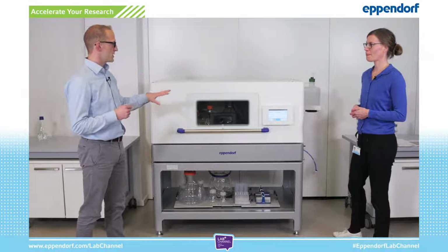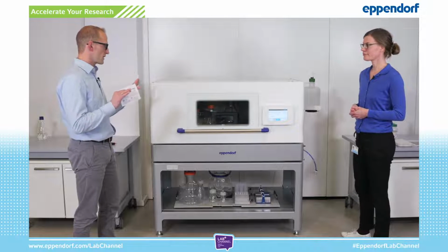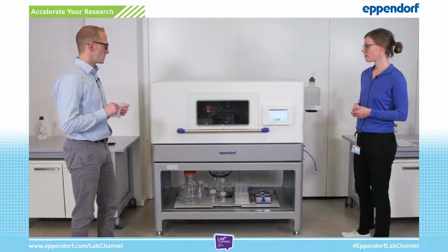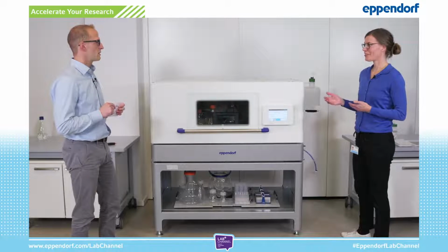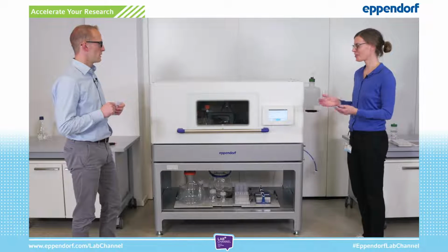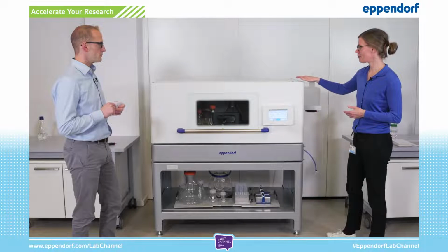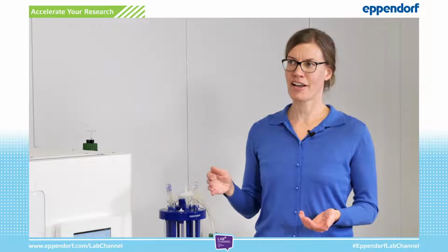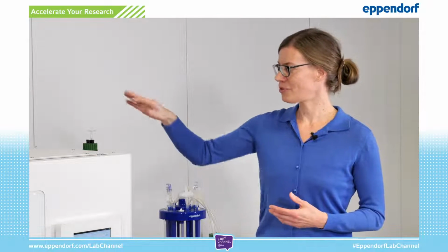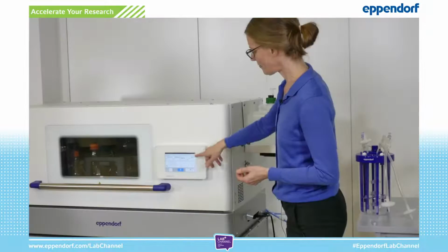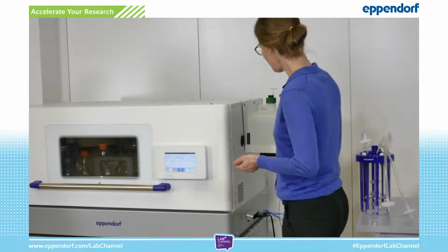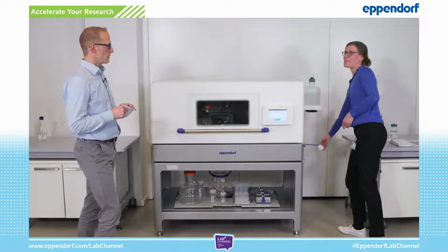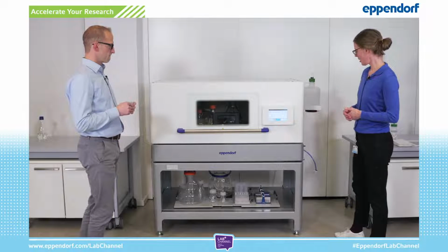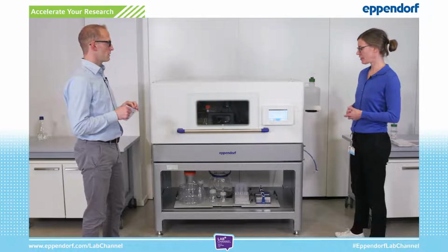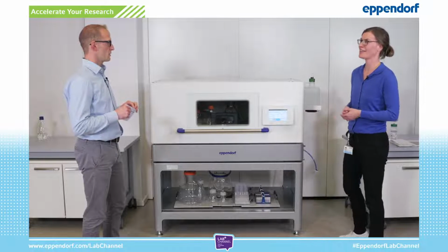Okay, and how is condensation then avoided inside? Because I guess condensation and contamination are a real issue with this whole water inside the chamber topic. So how is that avoided then inside? High humidity can cause condensation when you have temperature differences. We have our knowledge from the CellXpert C120i, our incubator, where we already optimized this six-sided direct heating concept. Plus, if the value exceeds 85%, we have a dehumidification function. I'm not sure if you see it in the back. There is a pump and that soaks air inside if it's going too high, exceeding the 85%. Here's also a HEPA filter so that only clean air gets inside. Yeah, okay.